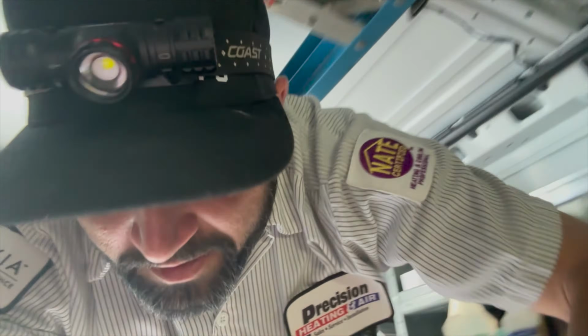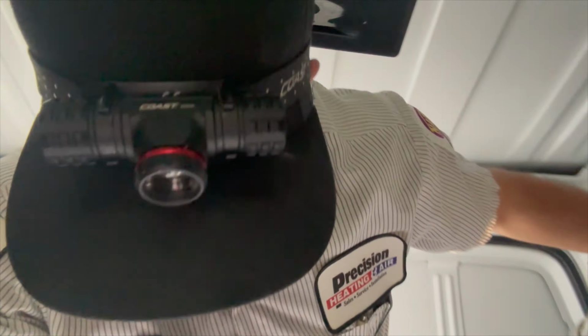Got in there, noticed there definitely wasn't a buzzing in the system. It has 240 volts but no 24 volts, so the transformer was definitely bad. We're going to see if that's the only issue - a lot of times storms or power surges can cause these things to go out. We'll keep our fingers crossed that's all it is and there's not a bigger underlying issue.